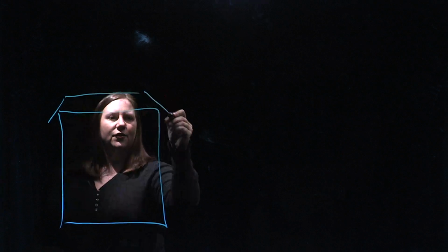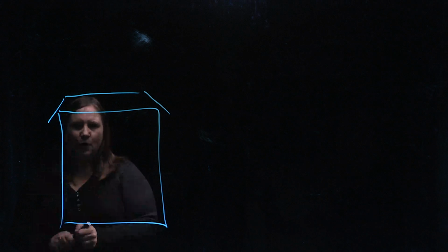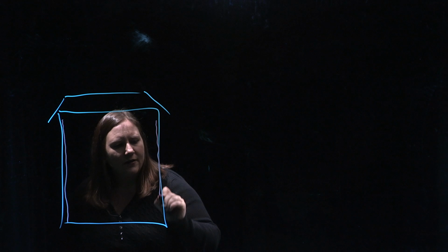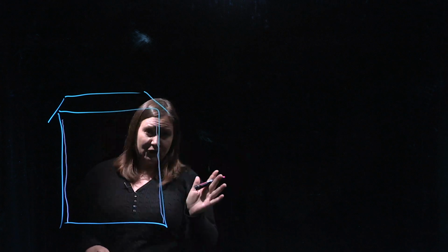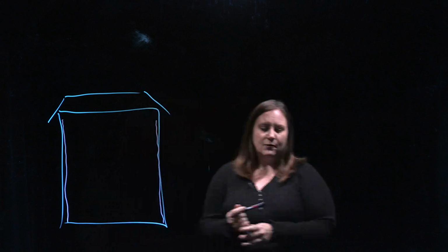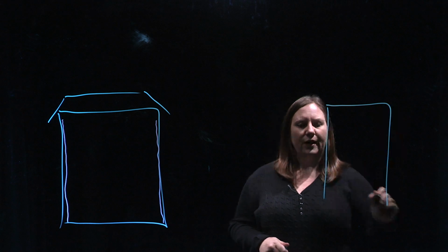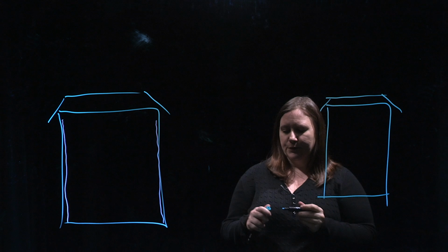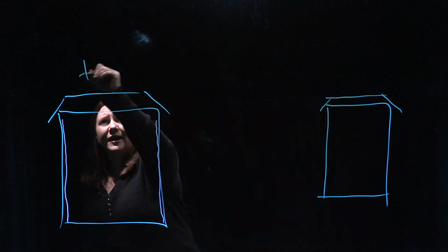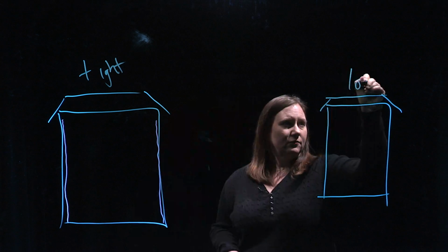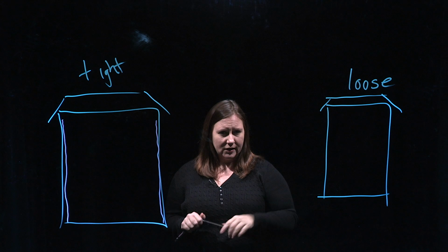Great. Now what we're going to do is consider the type of structure. Whether we're talking about a cottage, a house, or a shed in the backyard, any type of structure, we're concerned about how it's been built. If it has a vapor barrier or an air barrier, anything basically made out of plastic, that's going to be coming down and stopping infiltration and exfiltration, then it's going to be treated completely differently than a structure with no vapor barrier. So we are either going to call this equivalent to tight or equivalent to loose.